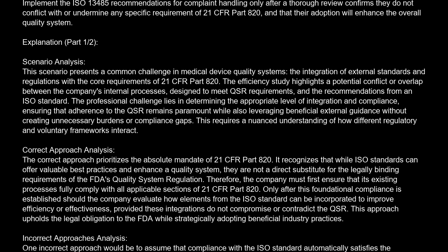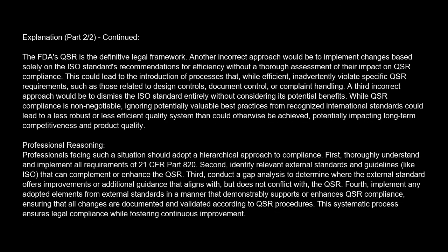Incorrect approaches analysis. One incorrect approach would be to assume that compliance with the ISO standard automatically satisfies the requirements of 21 CFR Part 820. This is a significant regulatory failure because ISO standards are voluntary and do not carry the force of law in the United States for medical device manufacturers regulated by the FDA. The FDA's QSR is the definitive legal framework.